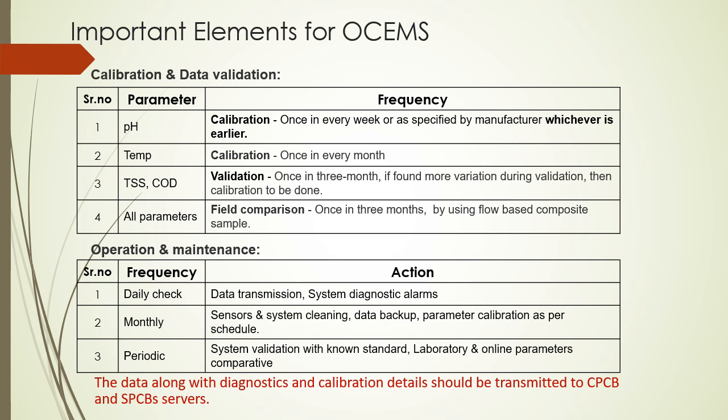When we did the OCEMS applicability check, wherein we have taken all the details from the CPCB website and created our own audit check sheet, we found that the calibration part was not up to the mark. So that's why I have included this, because once the OCEMS is installed, it's not that the work is done.